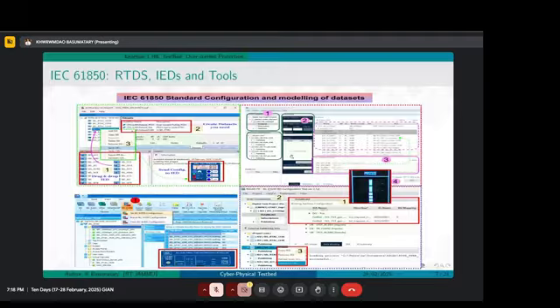The answer is, you have the AcSELerator Architect software with the IED palette, where different SEL devices and IEDs are listed. You drag and drop, for example, an SEL-751, to the project editor. Then you click it and configure the IP address of the relay and which Ethernet port it is connecting to.